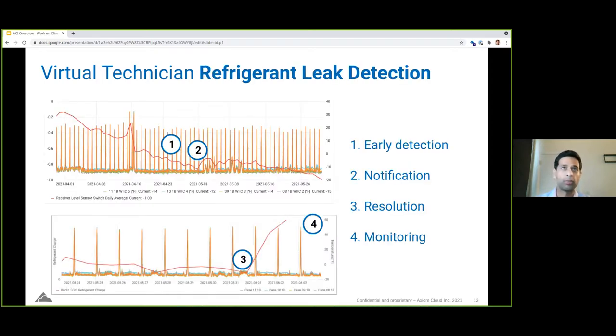This is a great example of virtual technician refrigerant leak detection. So what you're seeing here in these traces would be several cases having temperature traces, and this is over, of course, more than a month. And then this trace here would be what we're picking up from a receiver, which is a place where we can store refrigerant in the system. So essentially it's a surge tank for refrigerant.